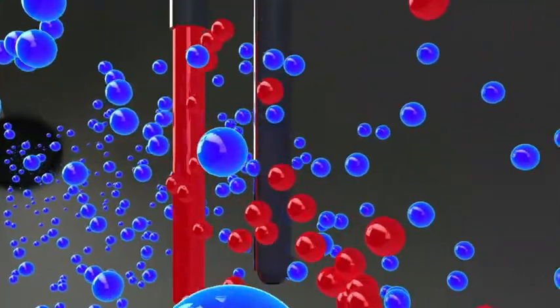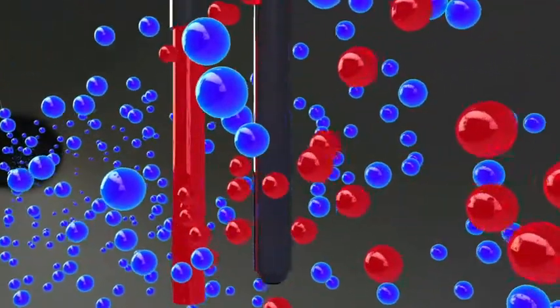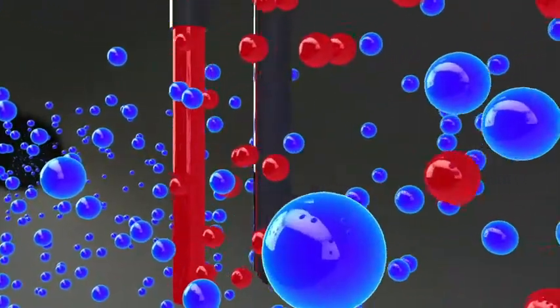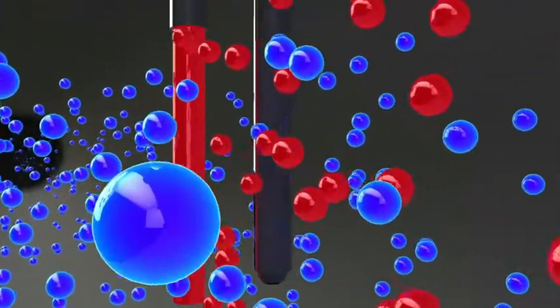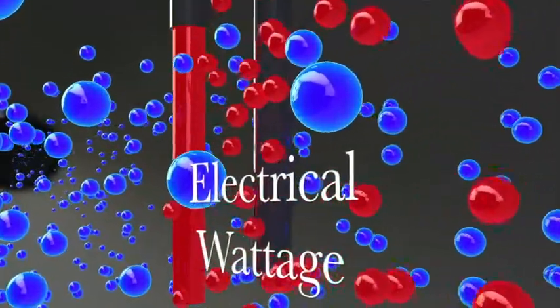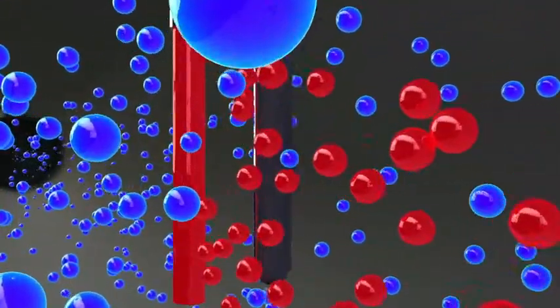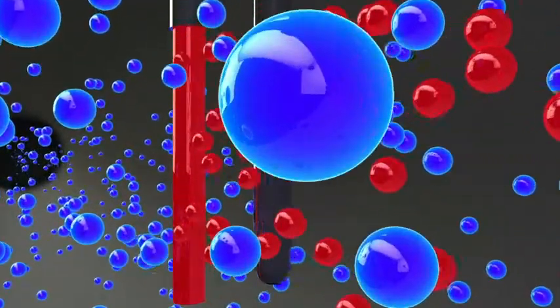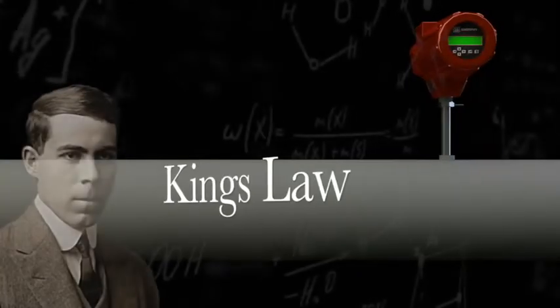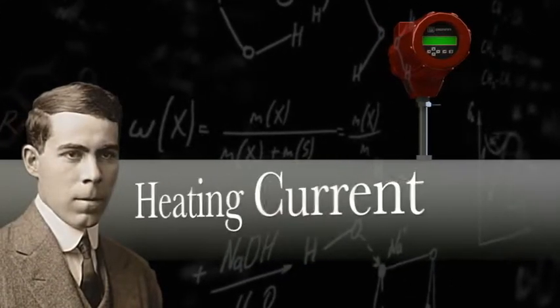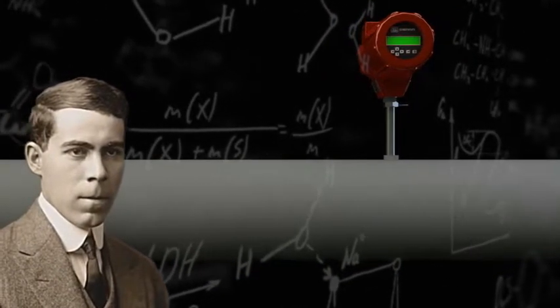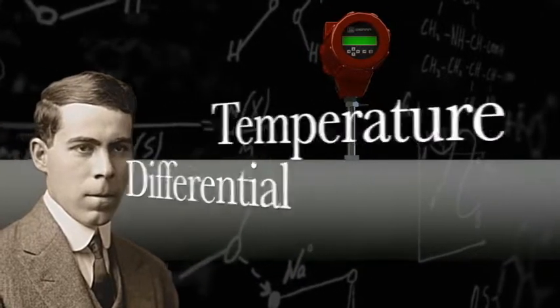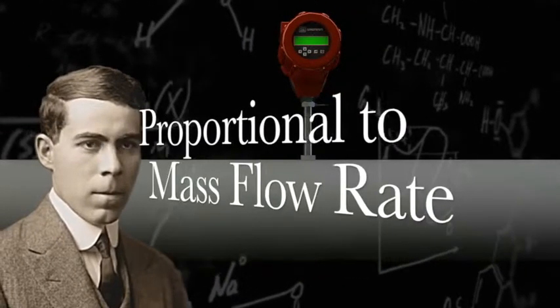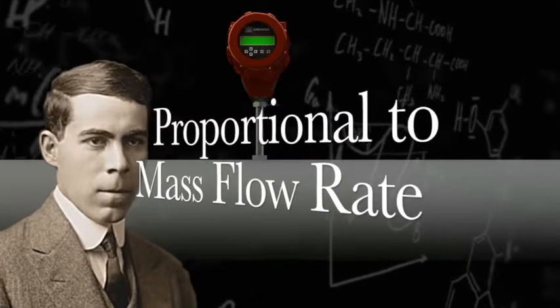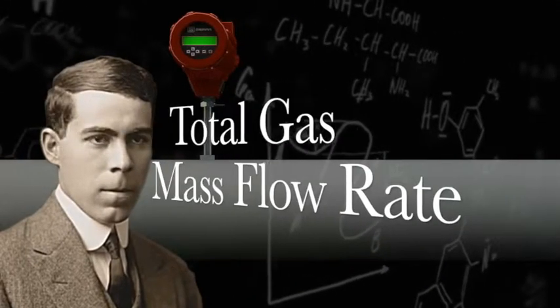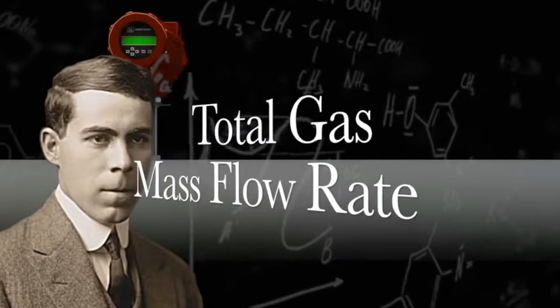So, now that we know the basic measurement principle, how is total mass flow rate of gas flowing through the pipe actually calculated? The meter's basic output is the electrical wattage carried away by the molecular flow. As the mass flow rate increases, the wattage increases. As described by King's Law, it turns out that the heating current required to maintain the constant temperature differential between the two sensors is proportional to the cooling effect caused by the gas molecules flowing by, and therefore is a direct measurement of total gas mass flow rate in the pipe.